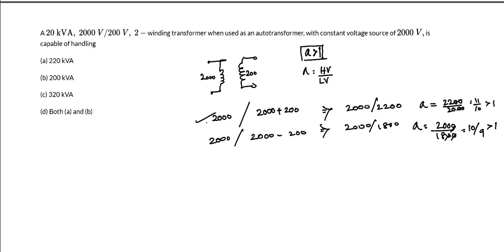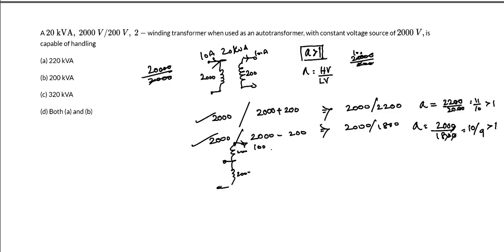So the rating is 20 kVA. 20,000 divided by 2000 gives 10 amperes here. 20,000 divided by 200 gives 100 amperes here. If I consider 2000 with additive polarity 200, what is the current flowing through the 200 winding? 100 amperes. So 2200 into 100 gives 220 kVA.